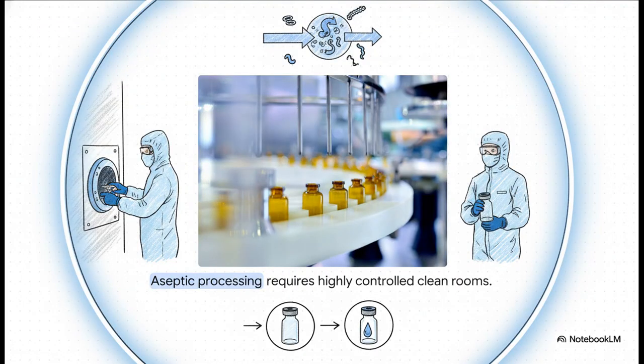And because we can't just blast the final sealed product to sterilize it, aseptic processing is kind of like a massive, highly choreographed puzzle. It requires every single individual component, the actual drug, the glass vial, the rubber stopper, to be sterilized totally separately, and then carefully assembled inside a highly controlled clean room. Liquid drugs are physically pushed through microscopic, sterile filters just to catch and remove bacteria. And the human operators have to be covered head to toe in sterile gowns, hoods, and goggles. Sometimes they even have to work through restrictive glove ports built into the glass, simply because, well, we humans are the single biggest source of contamination in the room.